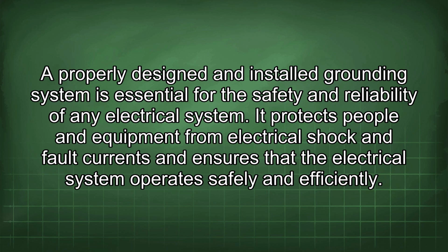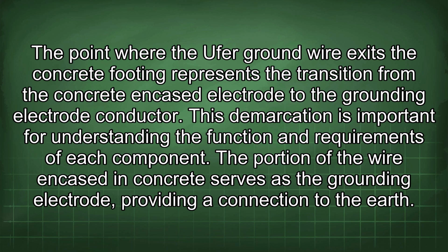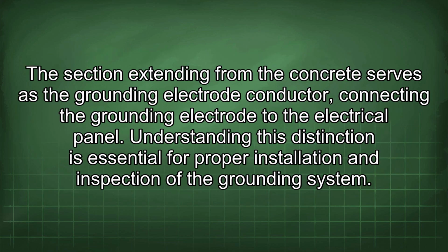and efficiently. The point where the Ufer ground wire exits the concrete footing represents the transition from the concrete encased electrode to the grounding electrode conductor. This demarcation is important for understanding the function and requirements of each component. The portion of the wire encased in concrete serves as the grounding electrode, providing a connection to the earth. The section extending from the concrete serves as the grounding electrode conductor, connecting the grounding electrode to the electrical panel. Understanding this distinction is essential for proper installation and inspection of the grounding system.